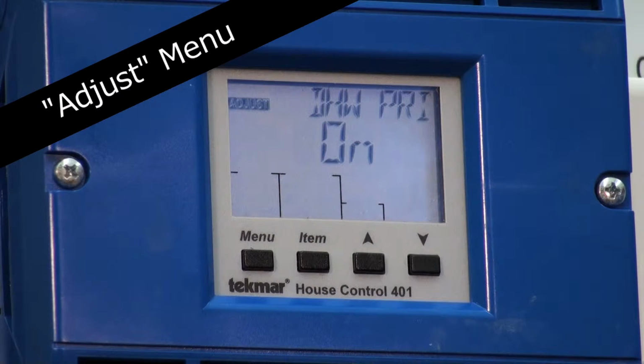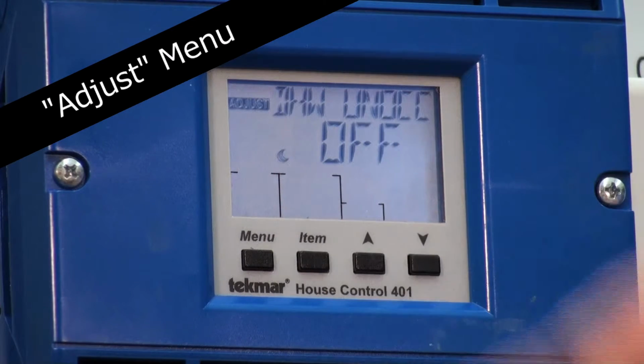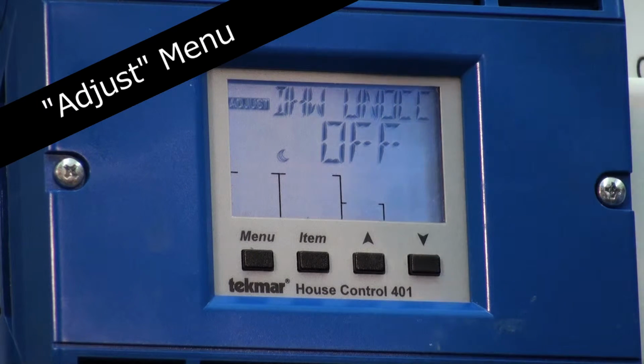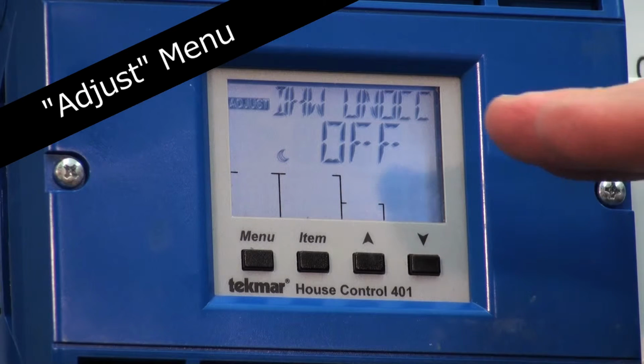Domestic hot water priority. With the 400 control, we're now taking control of the domestic hot water system also. We can have an aquastat tell it a call for heat or a sensor. Domestic priority is telling us that when it comes in, it's going to turn off the heating thermostats and go to 100% domestic hot water to get that tank up to temperature. Domestic hot water in an unoccupied mode is off. So you leave the house during the day, nobody's home, it turns the domestic hot water off.